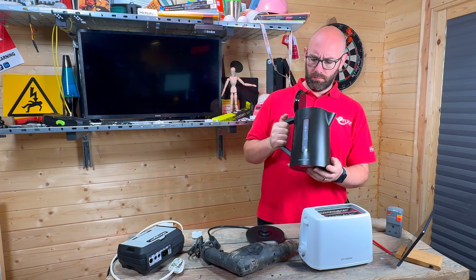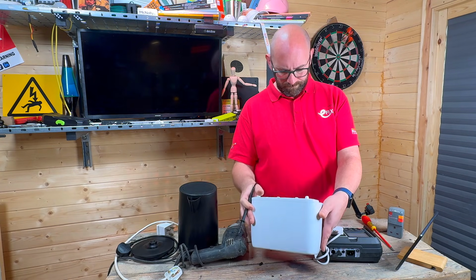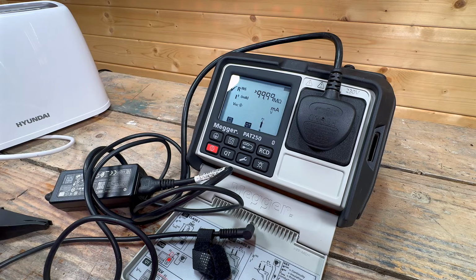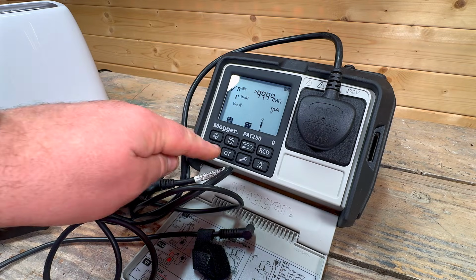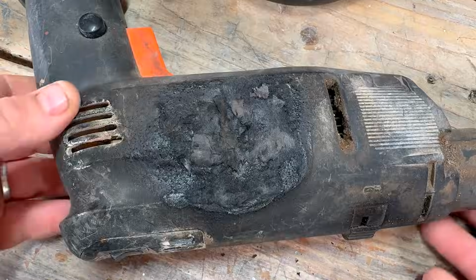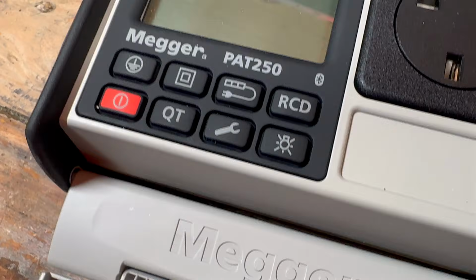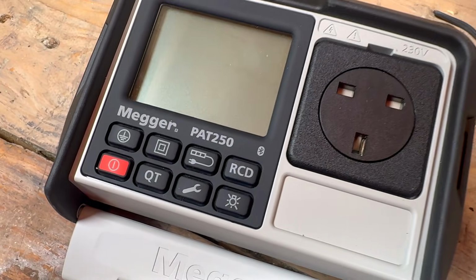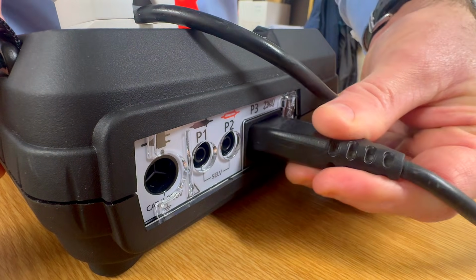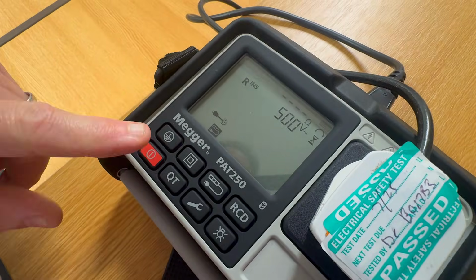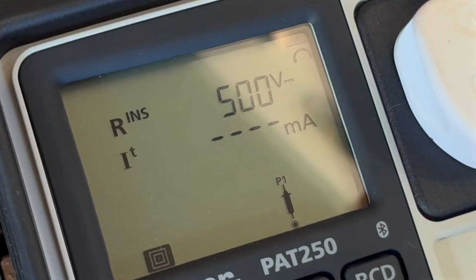A test operative needs to be able to identify the equipment classifications, because it's those classifications that determine the test procedure. Misidentification of classifications can lead to incorrect testing procedures, missed faults, and potential damage to equipment. We must also understand the tester that we are using, not just the button presses, but how the instrument works, its limitations, and when a particular test voltage or method may be unsuitable for the equipment being tested. Repeatable results depend on this knowledge, and so does not damaging the equipment during the testing procedure.